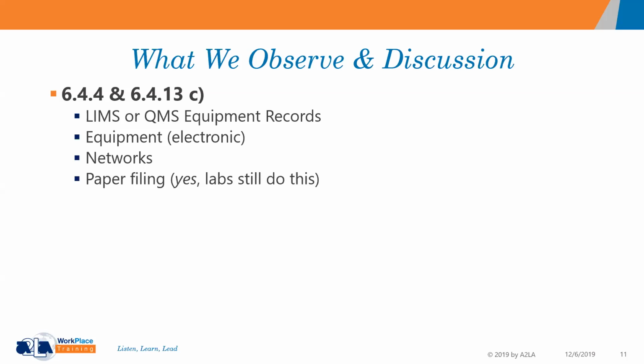The other thing that we also observed is that sometimes you can put those verifications within the electronics themselves. Sometimes those checks, like in the electronics world, they have auto cals, they have zero cals, and all those kinds of things. Some equipment has software that will actually track that information in there. Some assessors don't know that, and that's another issue that the accrediting bodies have to manage. But if that has the capability, there's no reason on earth why you can't store it there.